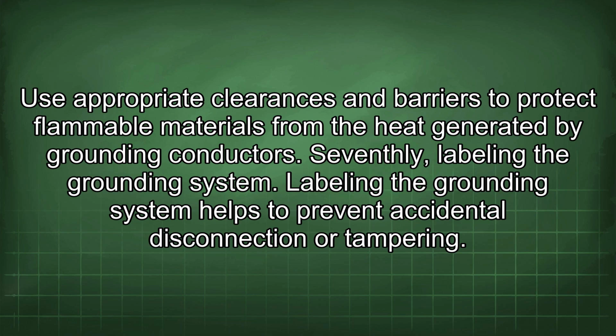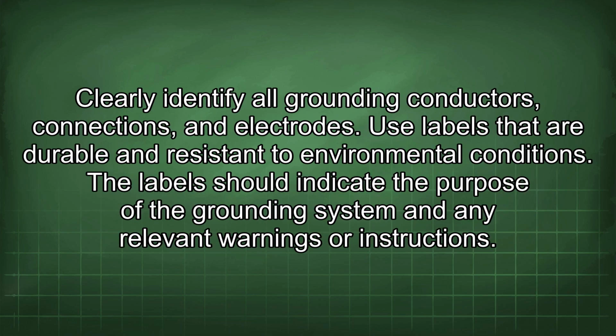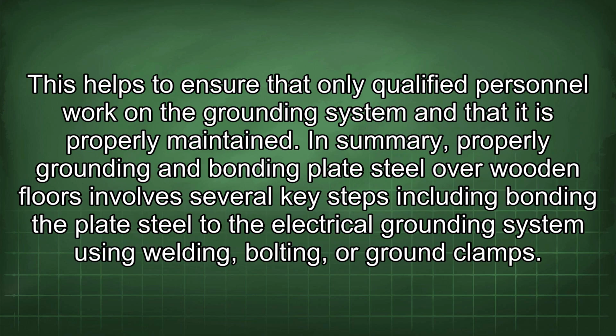Seventhly, labeling the grounding system. Labeling the grounding system helps to prevent accidental disconnection or tampering. Clearly identify all grounding conductors, connections, and electrodes. Use labels that are durable and resistant to environmental conditions. The label should indicate the purpose of the grounding system and any relevant warnings or instructions. This helps to ensure that only qualified personnel work on the grounding system and that it is properly maintained.